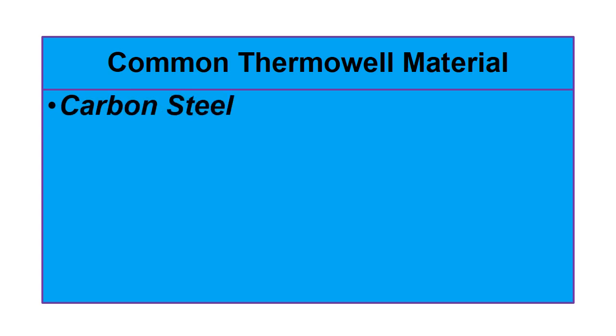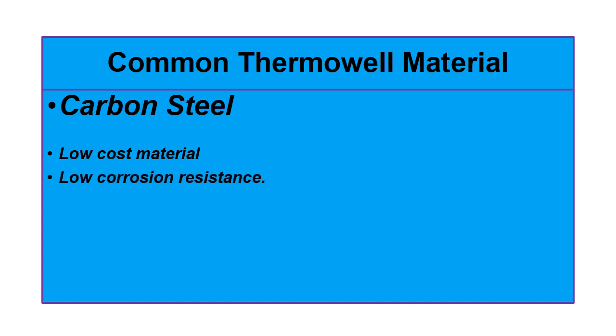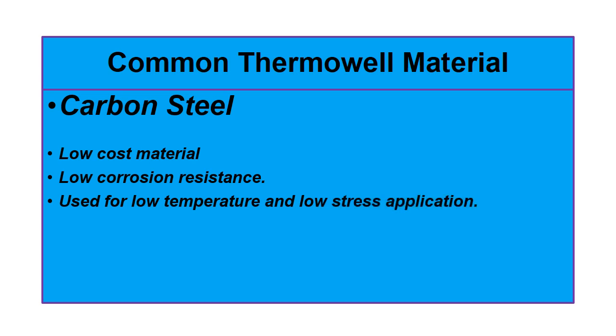The first material we are going to discuss is carbon steel. Carbon steel is a low cost material with low corrosion resistance. It can be used for low temperature and low stress applications. The carbon steel can be used for a maximum temperature up to 530 degrees centigrade.